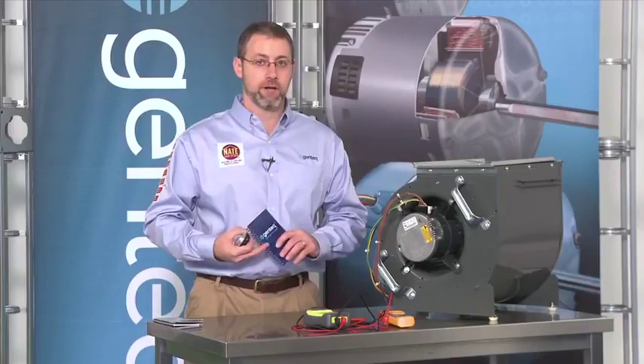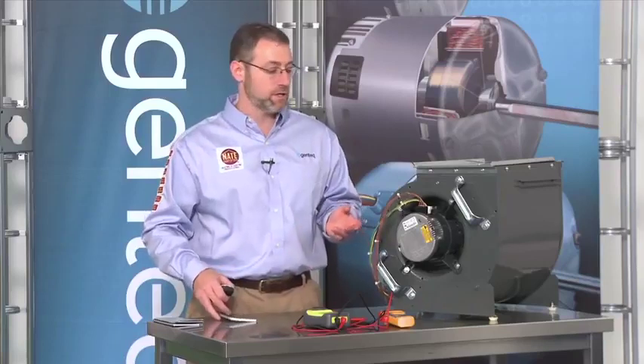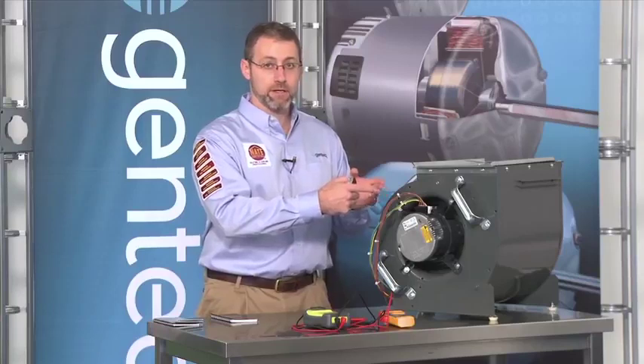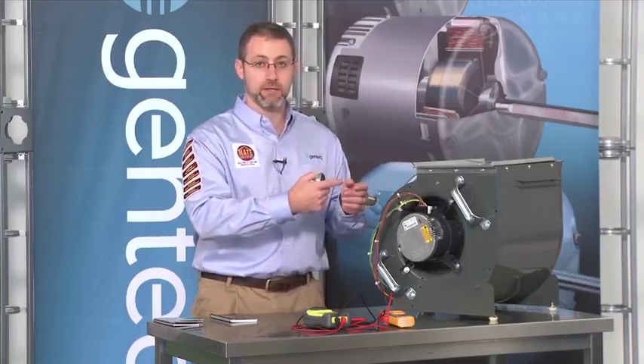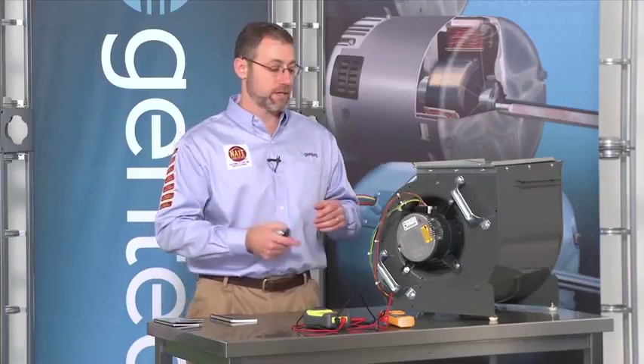In other words, I'm tripping the limit or freezing the coil. Well, those are typically airflow issues. Now an airflow issue that could be related to the motor would be I'm in tap 2 and I need to be in tap 3. In other words, I'm not in the right position I need to be in for the airflow that the manufacturer wants. In that case, I would need the OEM manual to tell me what position the wire should be in to get the proper airflow in the system.